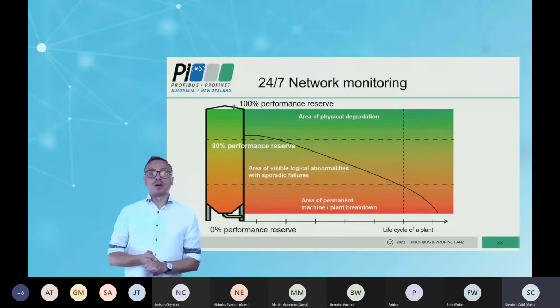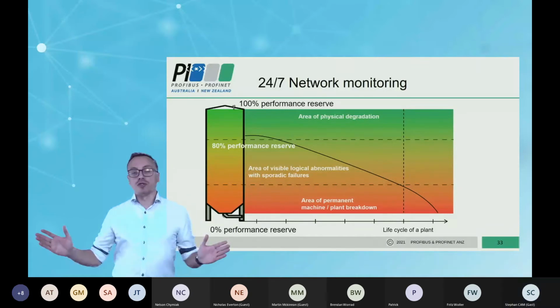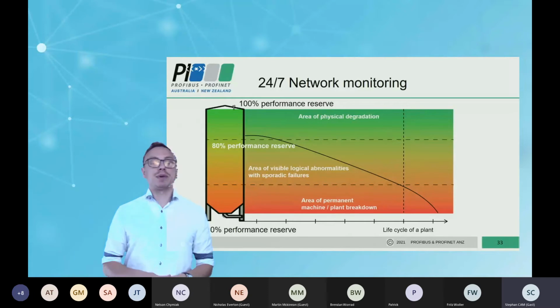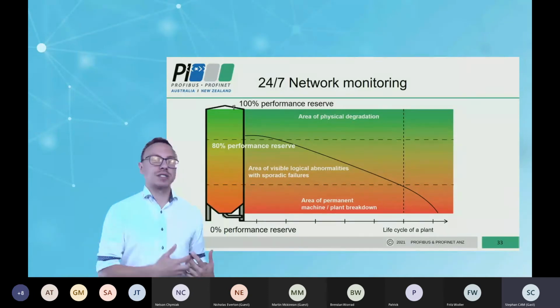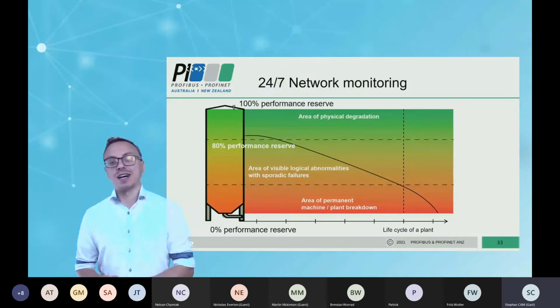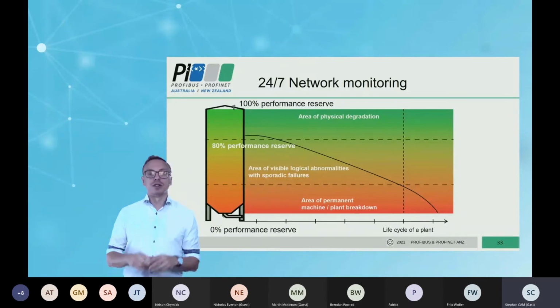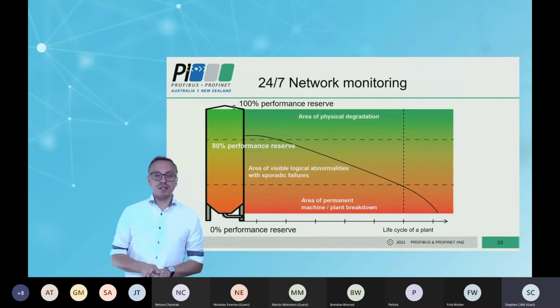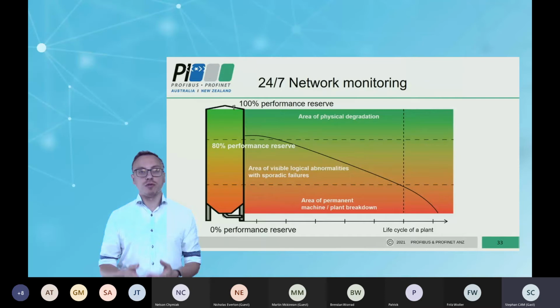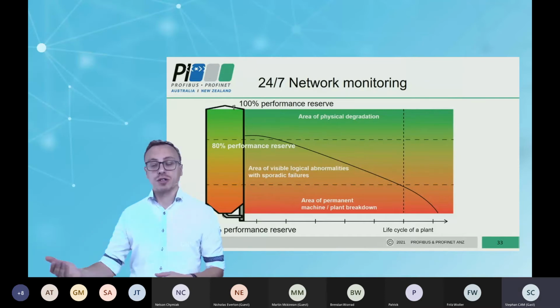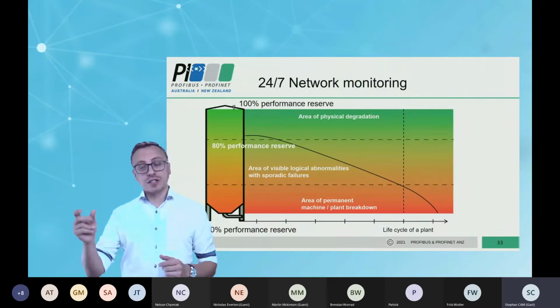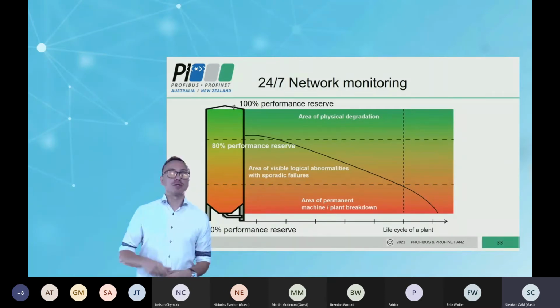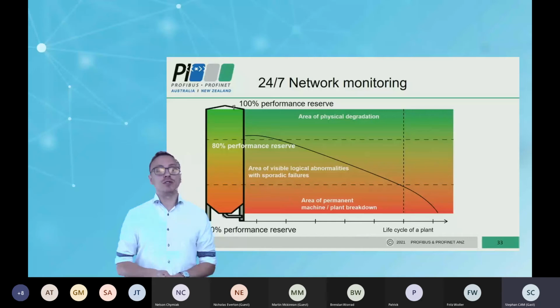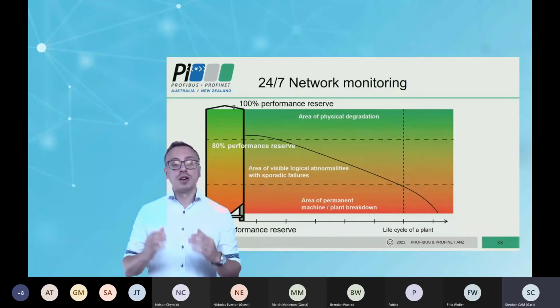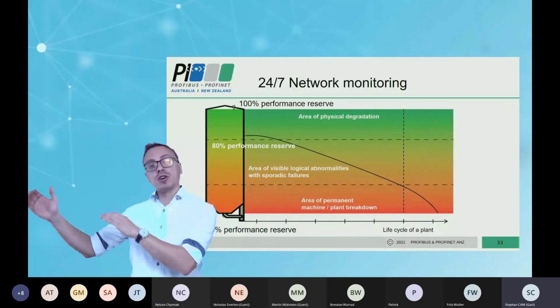You can do this measurement also over the long term. So in this case, the inspector can give you alerts before something happens. And this is normally the idea of the inspector, to use it as a long-term measurement tool. And the nice thing is, as I said, you get the alert before something happens because of your watchdog. The inspector will analyze your frames and will tell you, oh, now you have some error frames or some frame gaps in your network. And if you don't do something, you will get a stop of your plant in the future.